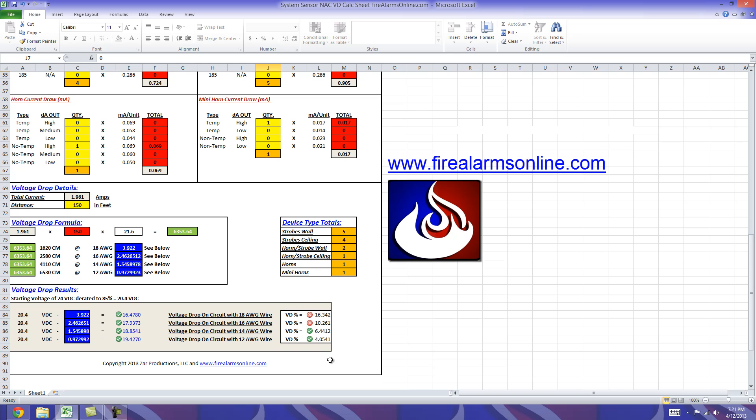This gives us our voltage for the circuit and then over here we have our voltage drop percentage for the circuit. And like we talked about, as long as we're above 16 volts here we're going to remain green, and as long as we're below 10% over here we'll be green.